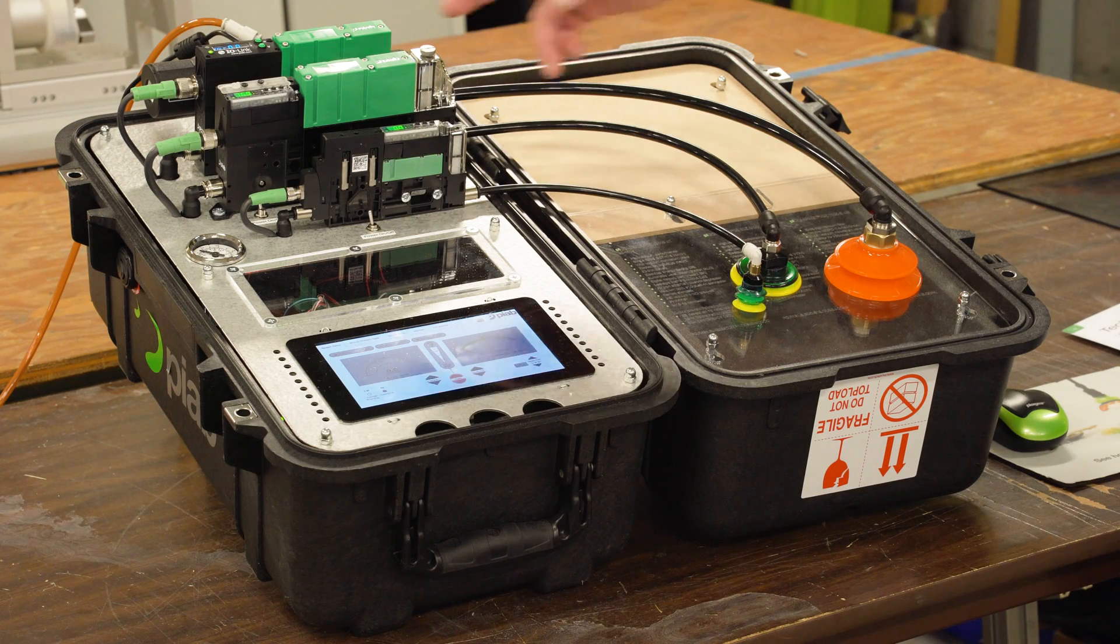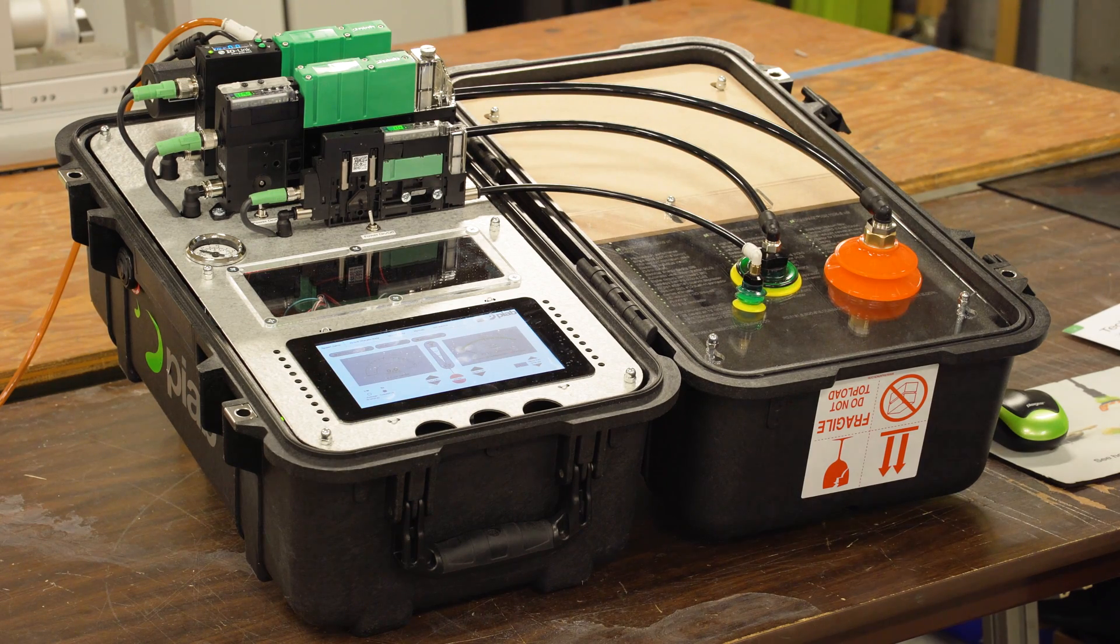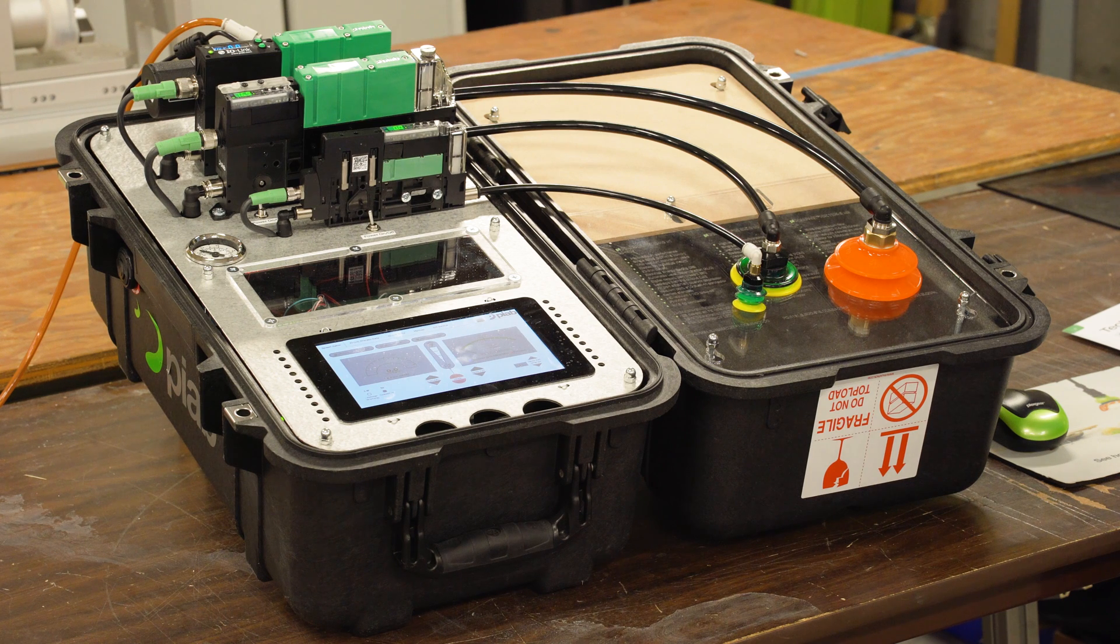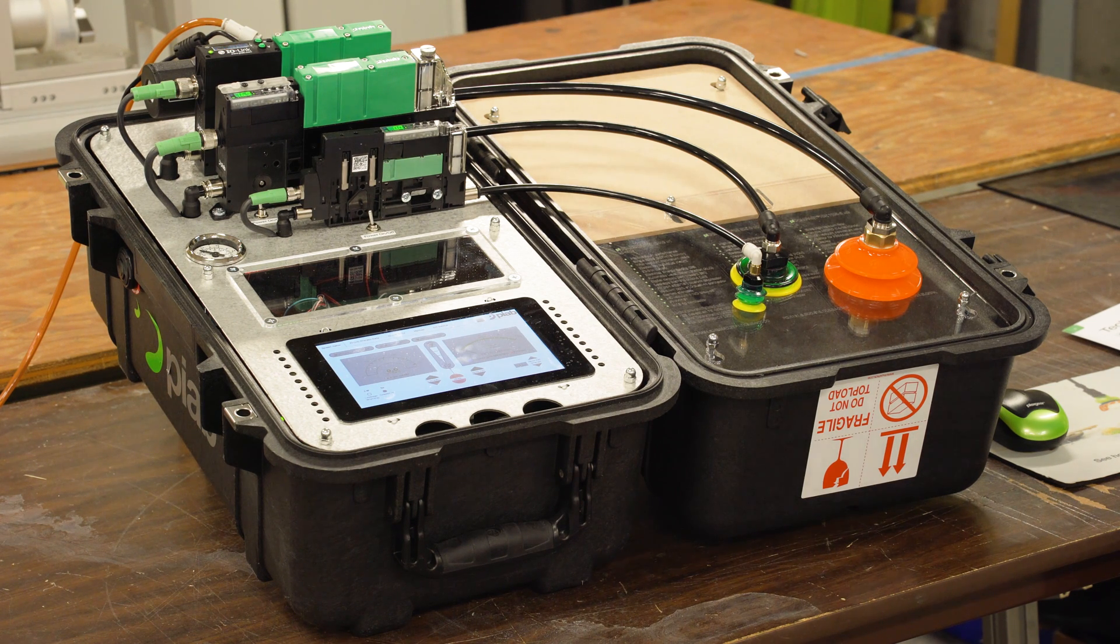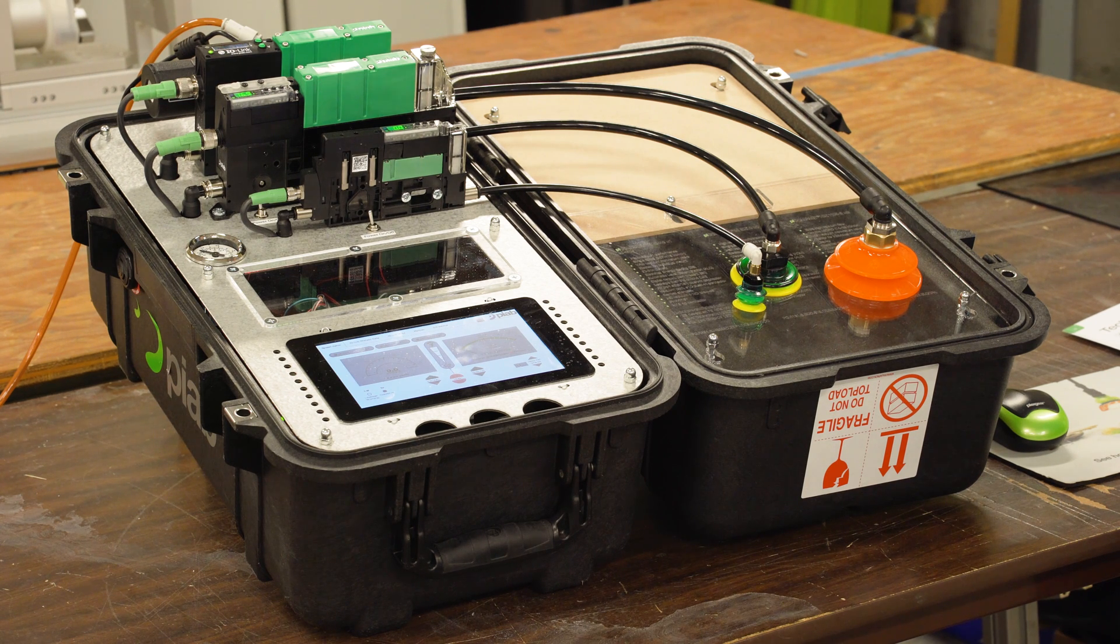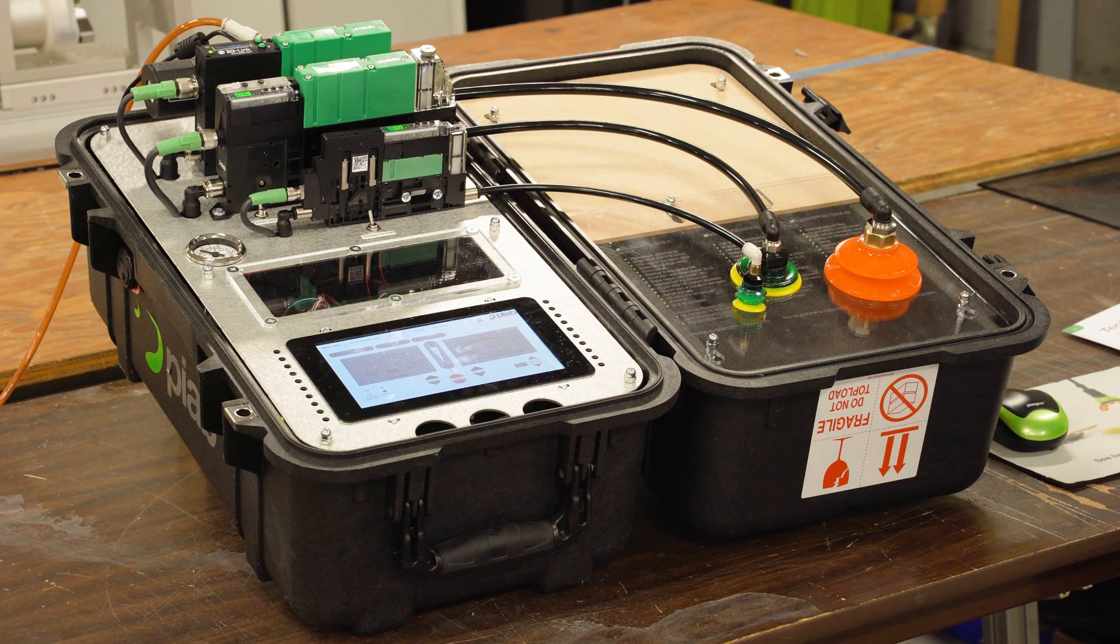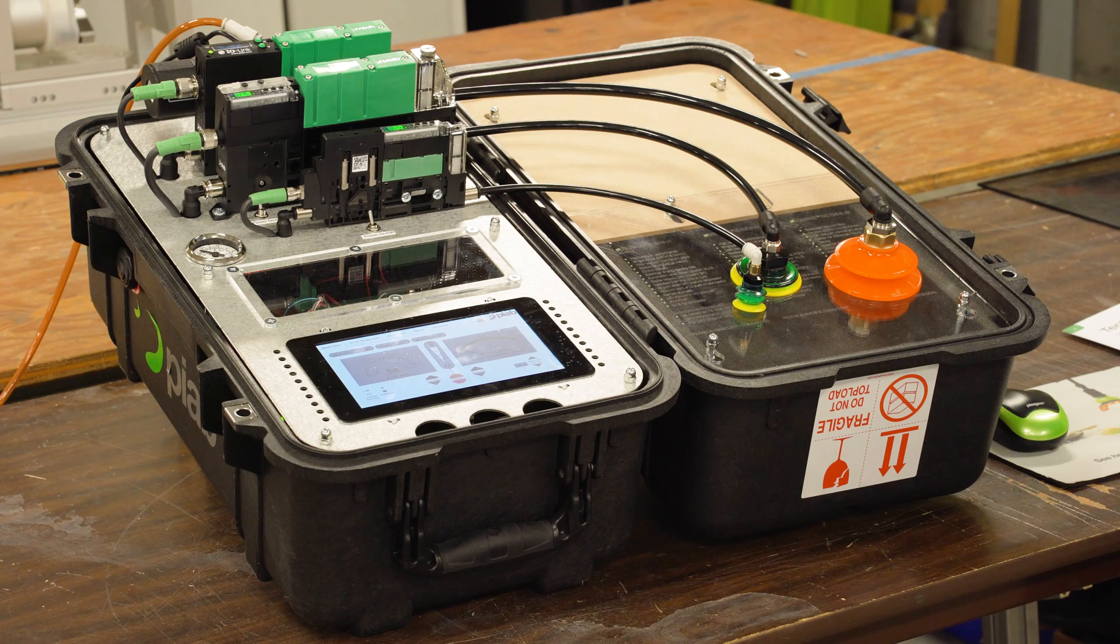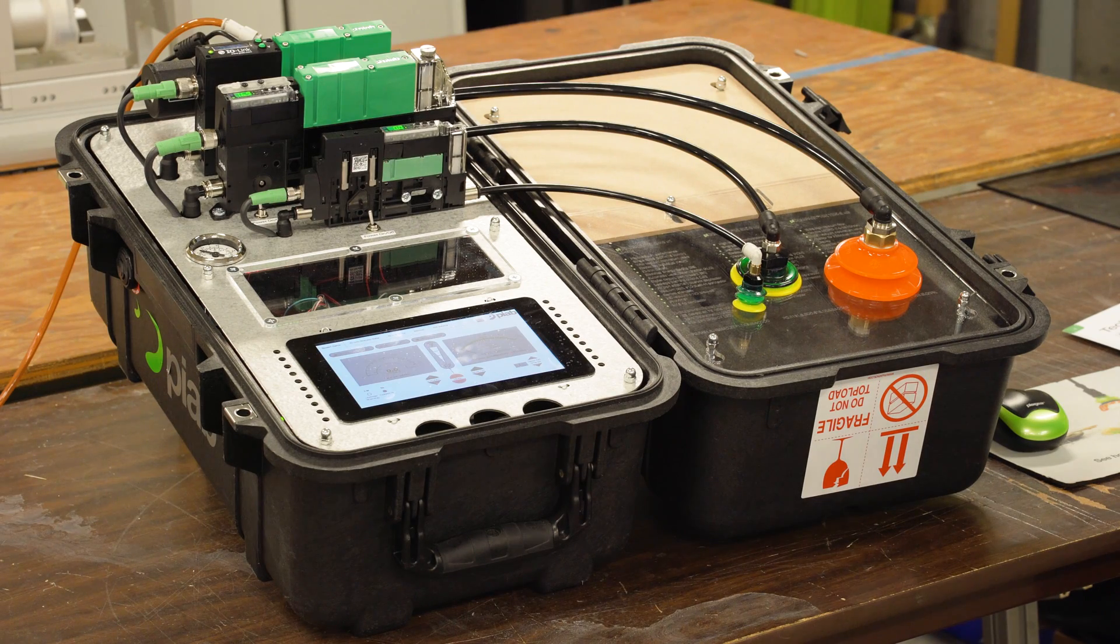This one, I haven't played with the settings here, but it's usually a set value. It's still set to inches of mercury, but a lot of times I talk kilopascals, it's more the levels I'm used to. But you can set it to say, get to negative 70 kilopascals max vacuum, low vacuum is negative 50 kilopascals, my switch output is negative 40 kilopascals. We can play with that today, too.